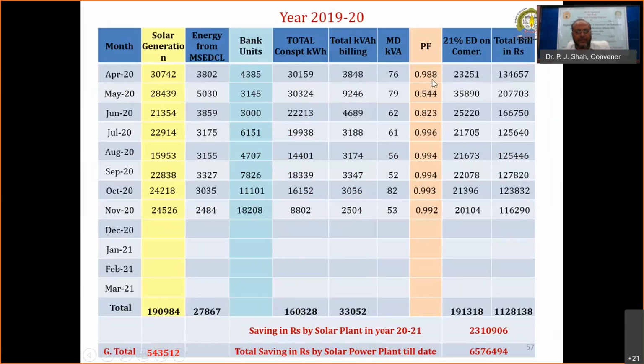However, because of the sudden lockdown, some capacitors remained connected in the system, and we observed that our power factor decreased from 0.988 to 0.544. It went to the leading side in the month of May because of the sudden lockdown, with nobody on the college premises to take care of the automatic power factor controller or the fixed capacitors. Because of this, the consumption is 5,000 units, whereas the billing kVA is 9,000.